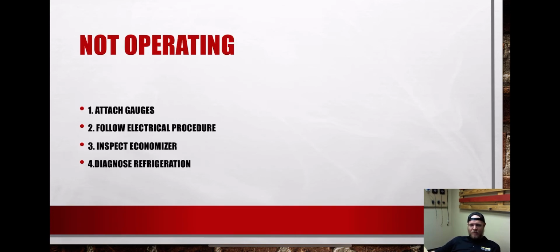So your unit's not operating, right? First things first, kind of attach your gauges. Follow your electrical procedure, inspect your economizer, and diagnose your refrigeration circuit. I always say that all the time. Tranes can be a little bit difficult to work on, especially when you're first starting out and getting your feet wet. Bring your gauges to the roof every service call you go on. I've known a lot of technicians that leave their gauges inside of the truck and then end up having to make a whole nother trip. Those things don't weigh very much, especially the new ones that you guys have. Throw them in your bag, throw them over your shoulder, whatever you got to do. Bring your gauges up. Save yourself a trip to the truck.